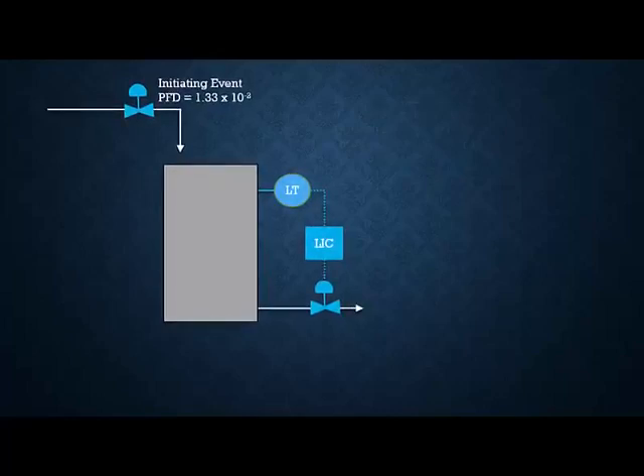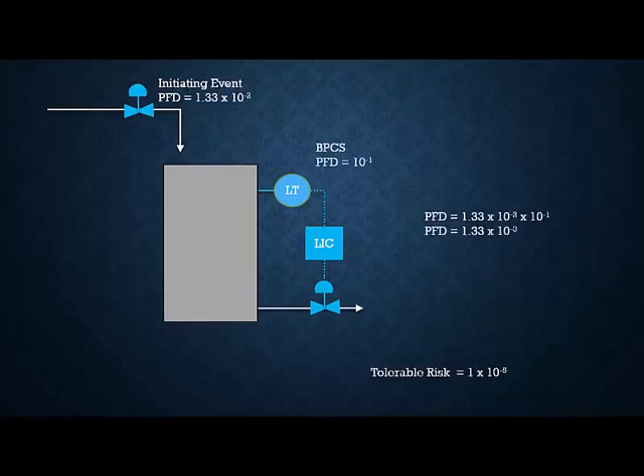In LOPA, you look at protection layers of what else can prevent that fatality from occurring. The next layer would be the BPCS system: a level transmitter, a level controller, control valve. Tank level gets high, control valve opens, tank level goes down, everything's good, right? But not quite, because the BPCS should work, but nothing works 100% of the time. A BPCS typically has a probability of failure on demand of 0.1. I'm going to go into that later, just trust me for now. So if its probability of failing is 0.1 and the initiating event is 1.33 times 10 to the negative two, you multiply them together and the odds of them both failing is 1.33 times 10 to the negative three. Better, but still not tolerable. You still have too much risk with this situation. You need another layer of protection.